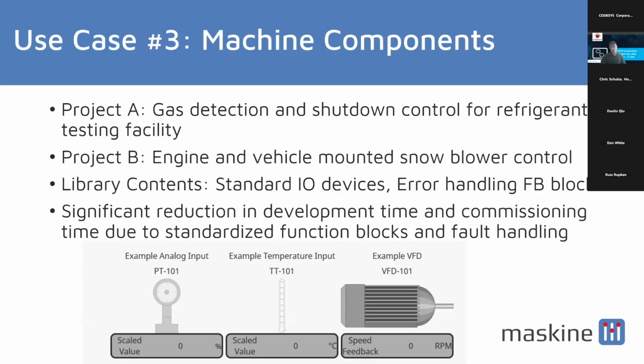In both projects, the engineer who developed the code didn't end up commissioning it. Because of this, the commissioning engineer had no issue identifying any bugs, since the logic was standardized and readable. He had trained on the library, knew it well, and had no problems. Since the project used JSON handling, we only needed one HMI device icon and one HMI faceplate, the JSON automatically handles the rest.